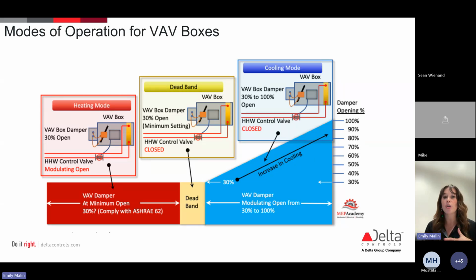In cooling mode, the control valve of our hot water heater is going to be closed. And that's where the VAV box damper is going to be open anywhere from 30 to 100%. So if you want more air being thrown through there, you're going to open that damper to 100%. That way you're getting more airflow.